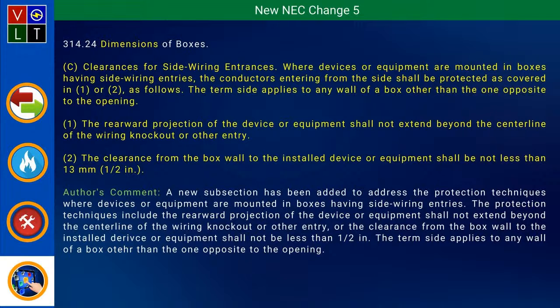So if you have your enclosure that's a half inch off the surface, then that would mean your raceway would have to be like 1 inch off the surface or something? No. What they're saying is that where you have the installed device or equipment, it shall not be less than a half inch from the back of that box. Oh, okay, I got you.